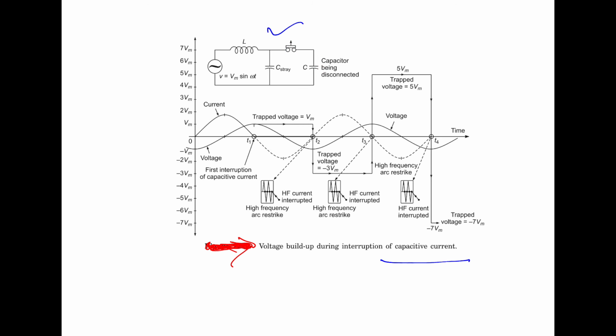Now, because of the capacitor, the current in this case leads the voltage by an angle of 90 degrees. Thus, at the current zero instant T1, the voltage is at its peak, that is Vm, and action starts at the instant T1. At this instant, the system voltage as well as the capacitor which is being disconnected are at the voltage plus Vm. So the voltage across the circuit breaker contacts in this case is equal to 0. This is obvious from this diagram.